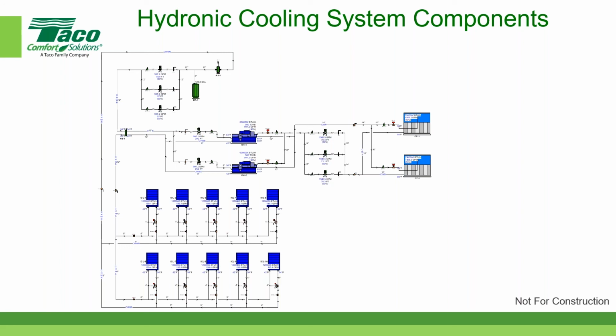So when you think of a cooling tower and you think of condenser water, there's two functions of a cooling tower in the wintertime. So cooling towers, and let's just talk about specifically open cell cooling towers for a moment. Open cell cooling towers, by their very nature, are exposed to the atmosphere, even in freezing conditions. And so many cooling towers operate in severe cold weather in the wintertime to provide free cooling, usually through a plate and frame heat exchanger.